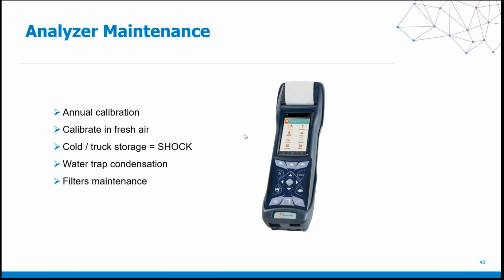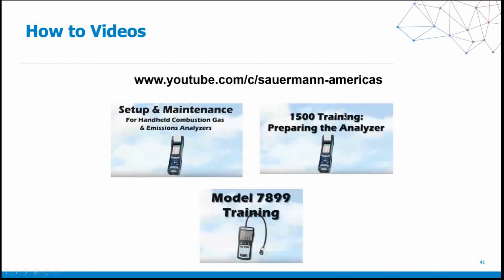Make sure that you check your filters. You check the filter on your HVAC system in your home. Well, guess what? You have to look at and monitor the filter on your combustion analyzer as well. That is very, very important that you do that. A dirty filter creates a dirty operating condition for the analyzer.